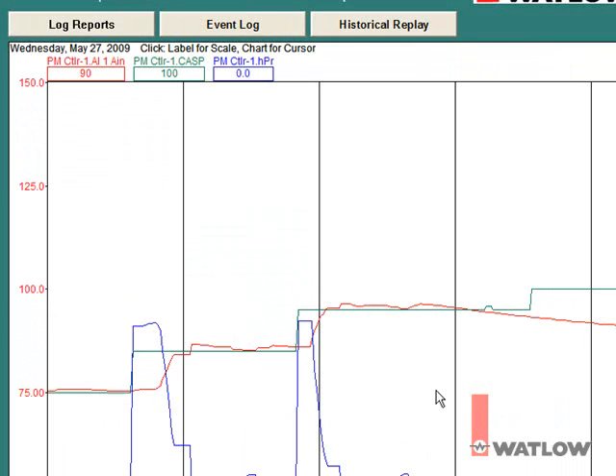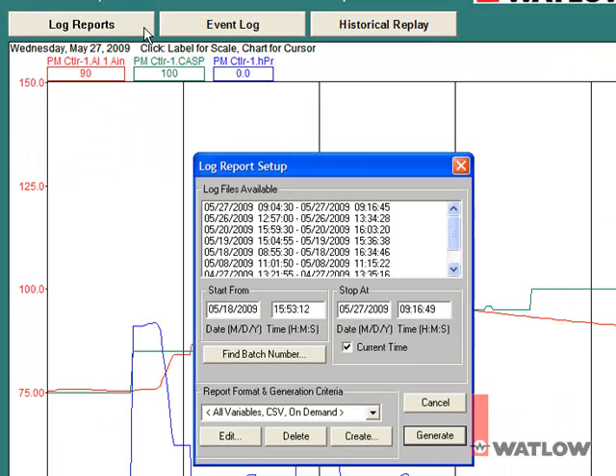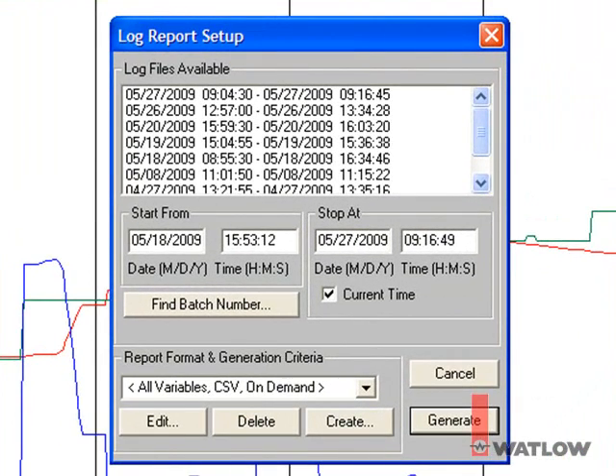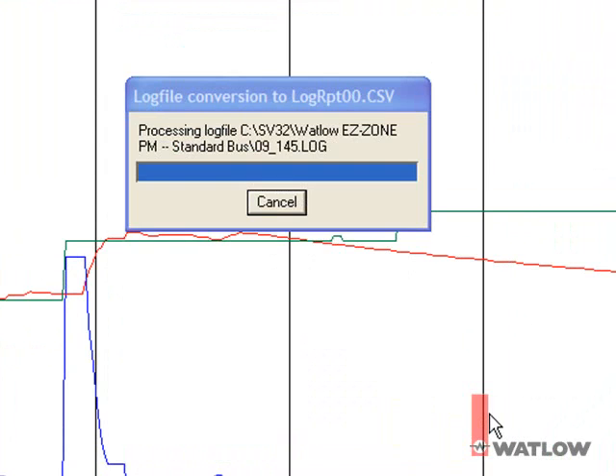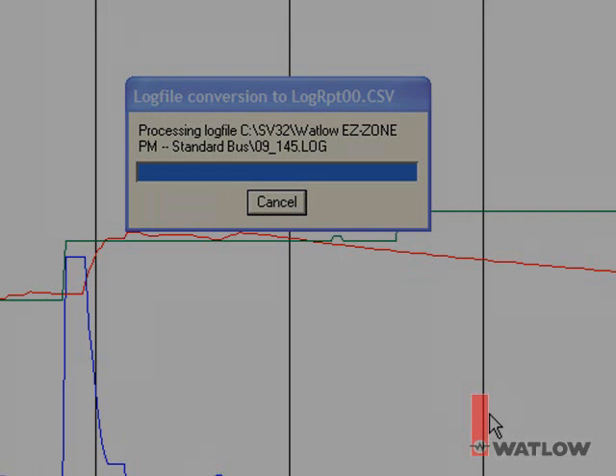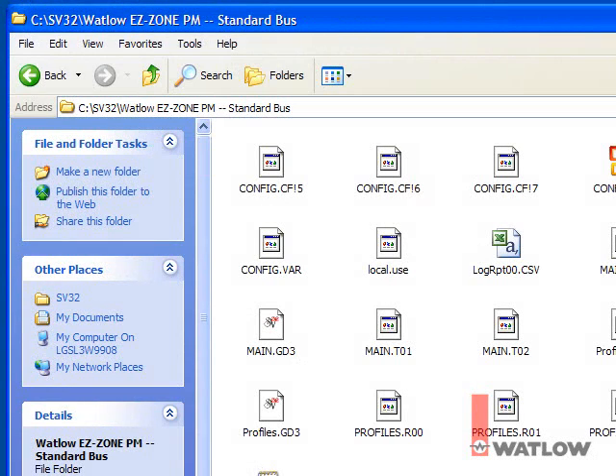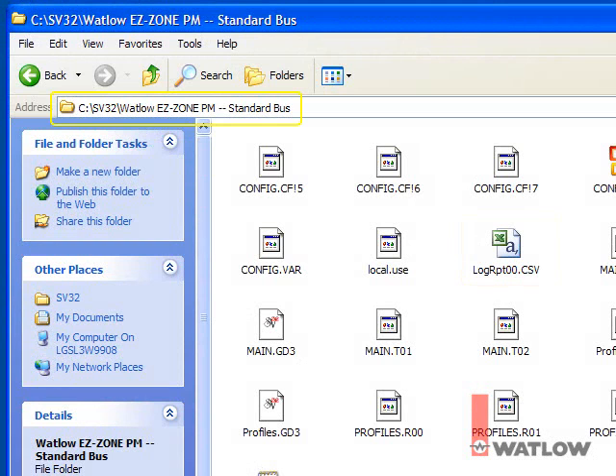To export a data log report that can be used in other programs such as Microsoft Excel, click the Log Reports button. Select one of the date and time ranges during which data was recorded, then click Generate to output the report. By default, the data is exported to a file named log rpt, the two-digit serial number, dot csv. This file is located in the configuration folder under the SpecVue program folder. Normally the program folder is C:\sv32, and in this case the configuration folder is Watlow EZ-ZONE PM Standard Bus.